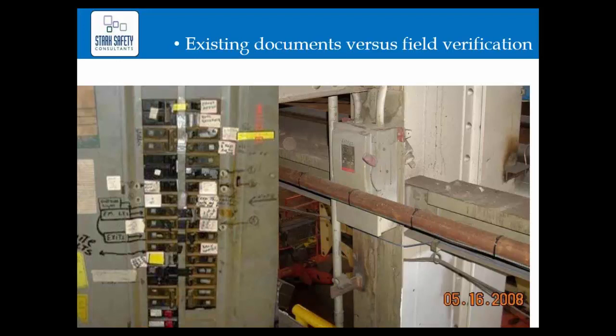On the right, we see evidence where someone had stuck copper tubing right up against this disconnect switch. Had we not field verified, we wouldn't have known this issue existed, and it looks like there might even be a case where the switch couldn't be turned off, let alone opened for servicing.